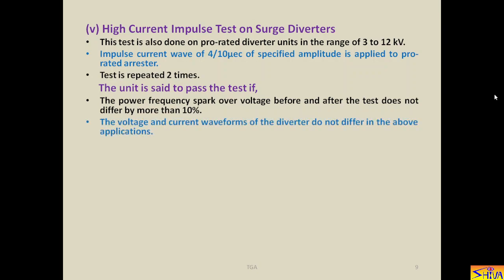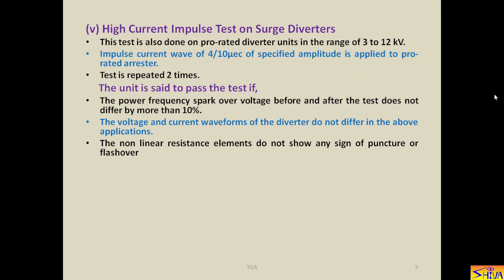The voltage and current waveforms of the diverter do not differ in the above applications. The nonlinear resistance elements do not show any sign of puncture or flashover. So we perform the test on the prorated unit with impulse current of standard wave. For impulse current, there are two standards. One is 8 by 20 microsecond, and for maximum discharge current testing, it is 4 by 10 microsecond duration. So after performing the impulse current wave test 2 times, we perform these 3 tests, and if these tests are successful, then we say that the unit has passed the high current impulse test.